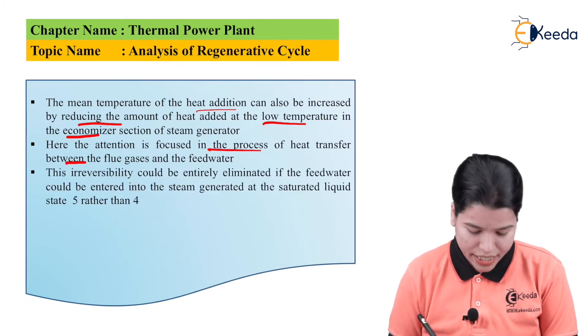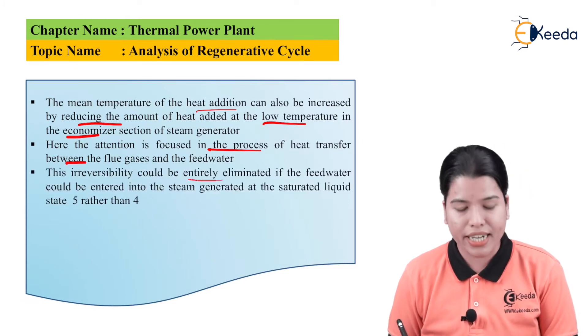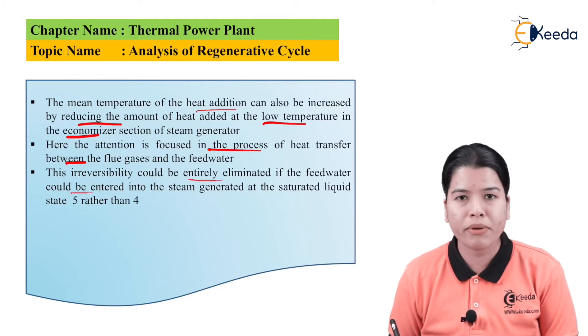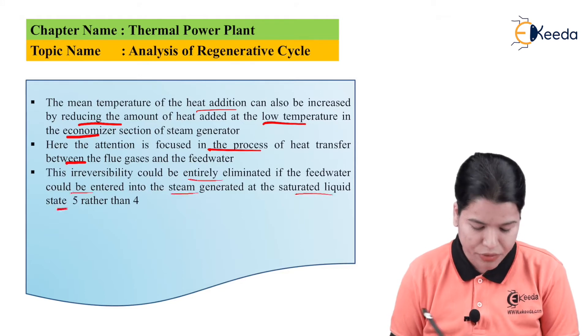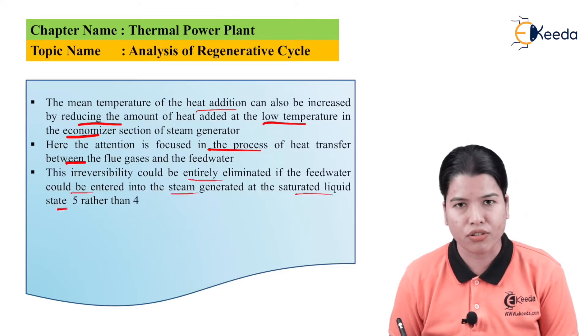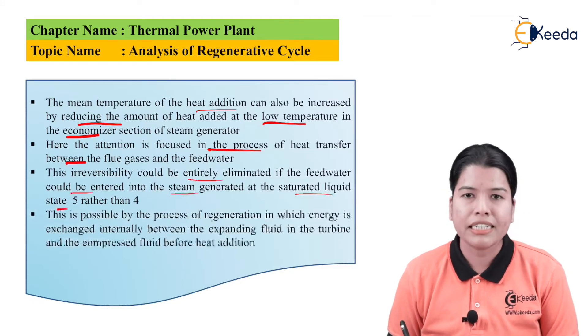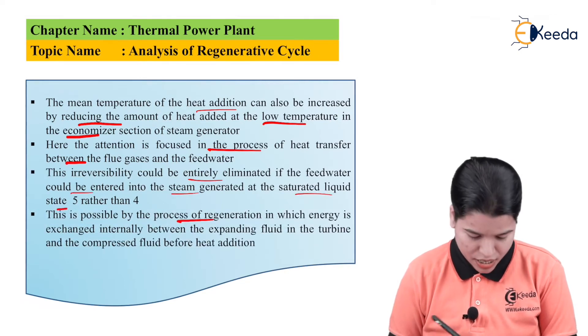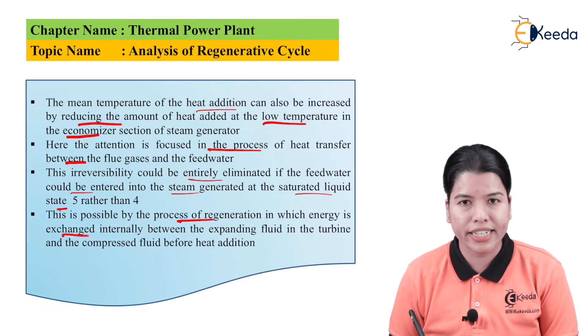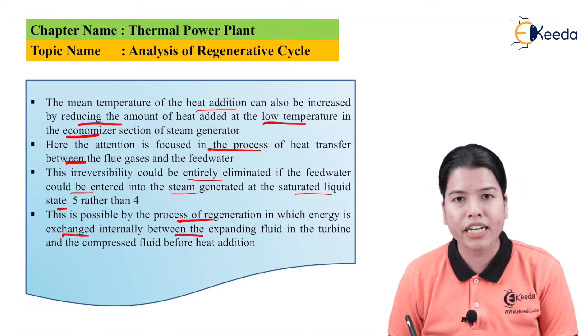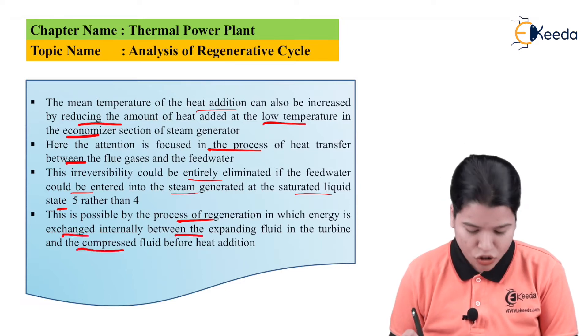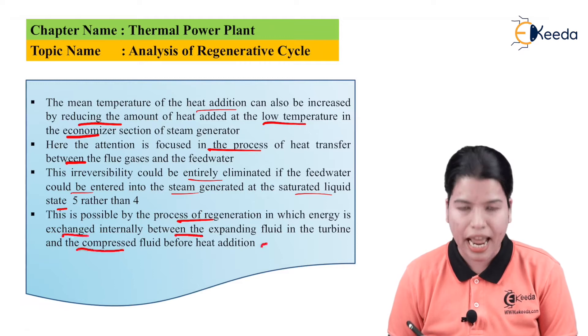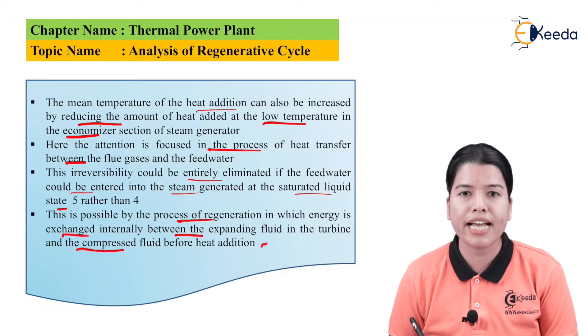This irreversibility could be entirely eliminated if the feedwater could be entered into the steam generator at a saturated liquid state 5 rather than 4. This is possible by the process of regeneration, in which energy is exchanged internally between the expanding fluid in the turbine and the compressed fluid before the heat addition. This process is called regeneration.